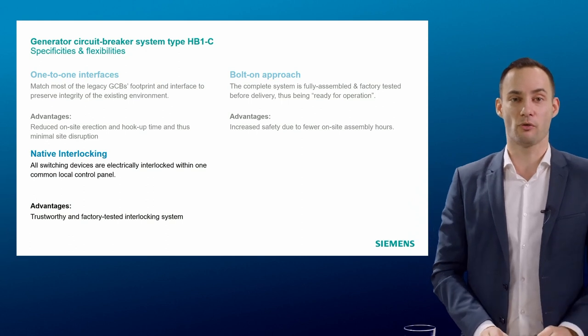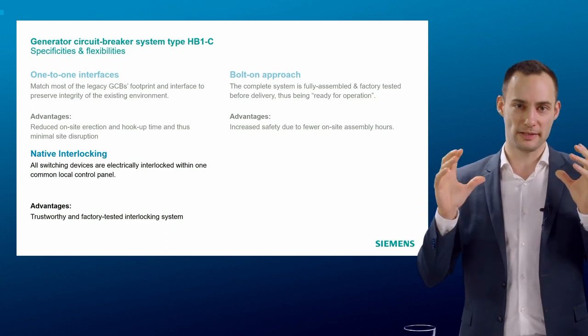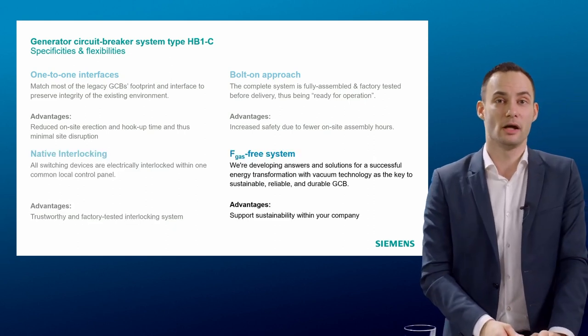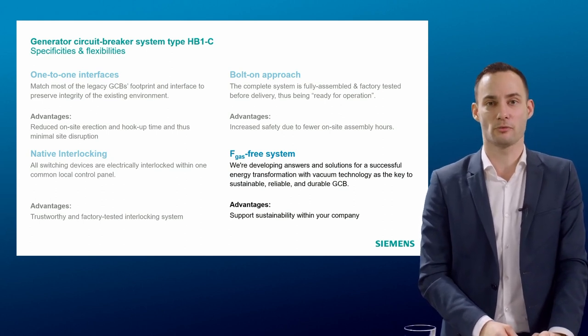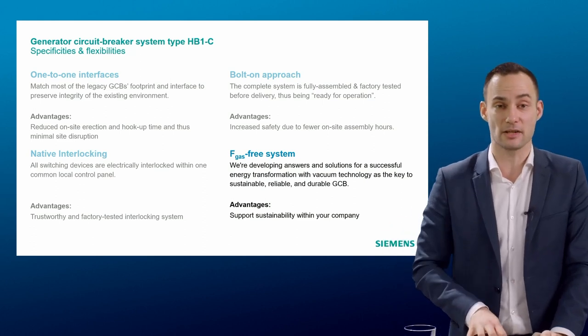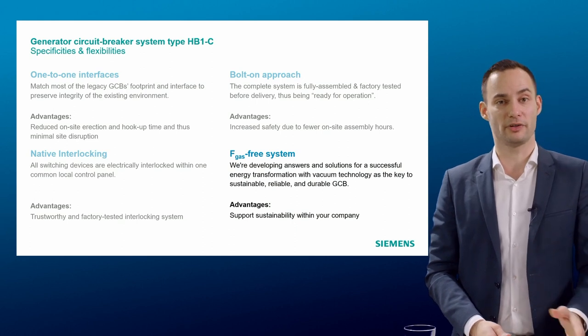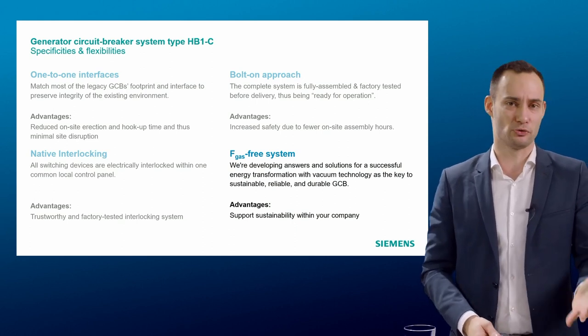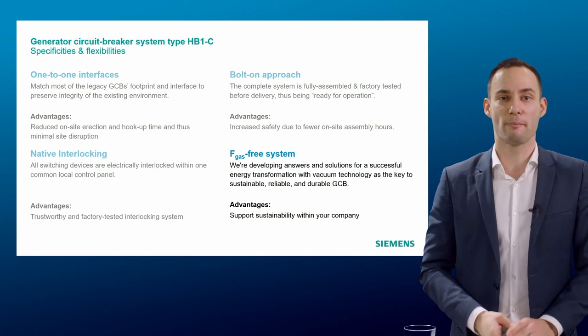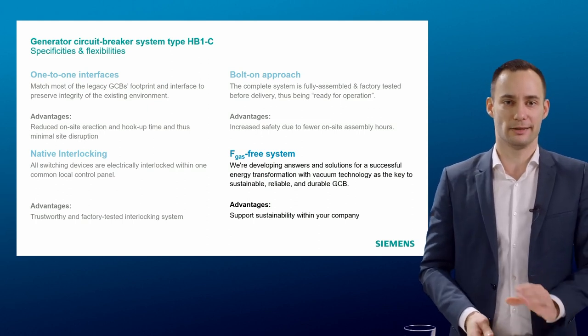We also supply all this equipment together with a fine-tuned interlocking approach — all equipment on the module is delivered interlocked together. Last but not least: the F-gas free system. There is now much more stress worldwide on F-gas, especially in Europe where new regulations are coming — not yet extended to the GCB application, but it will come soon for medium voltage applications in primary and secondary GIS switchgear. That's why, in addition to the CO2 footprint impact of SF6, we believe going to market with an F-gas free solution is the right approach.